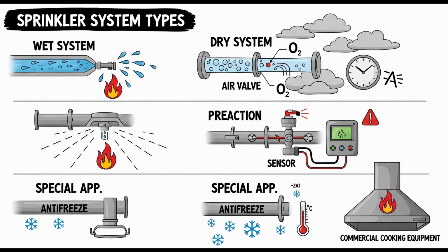So one sprinkler head goes off over a fryer, and it instantly cuts the gas and or electricity to everything it's supposed to protect under that hood and maybe even other gas appliances nearby. And someone physically has to go and flip a switch or turn a valve back on to restart anything after the fire department leaves. Precisely.